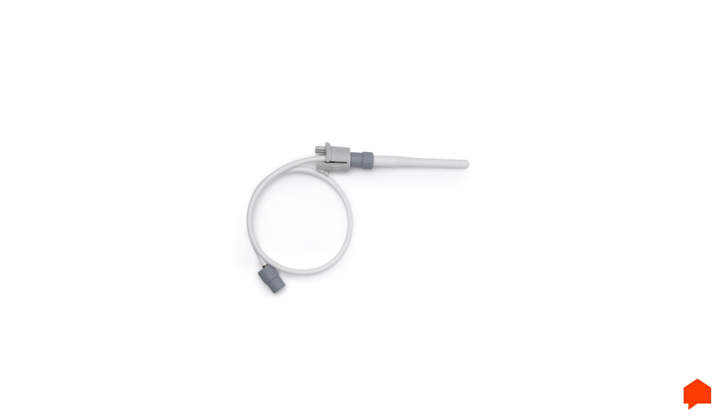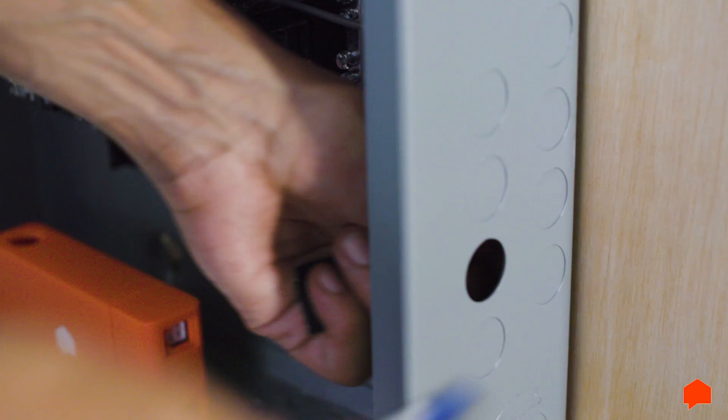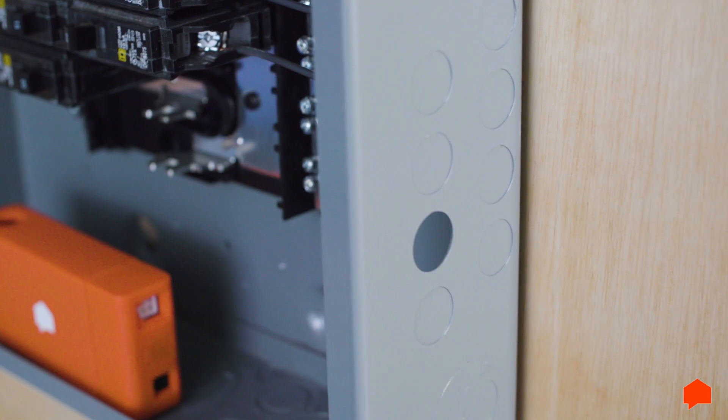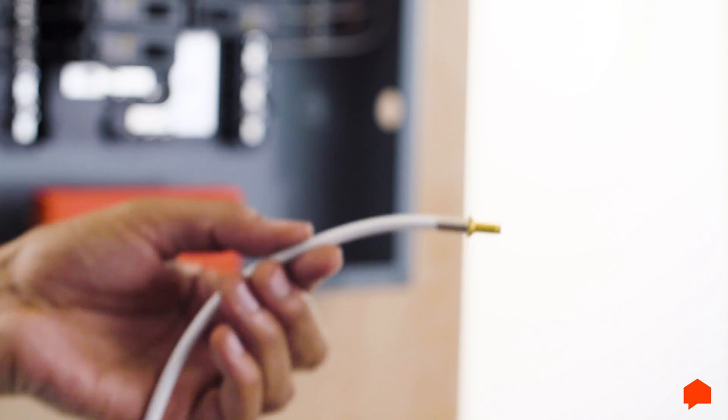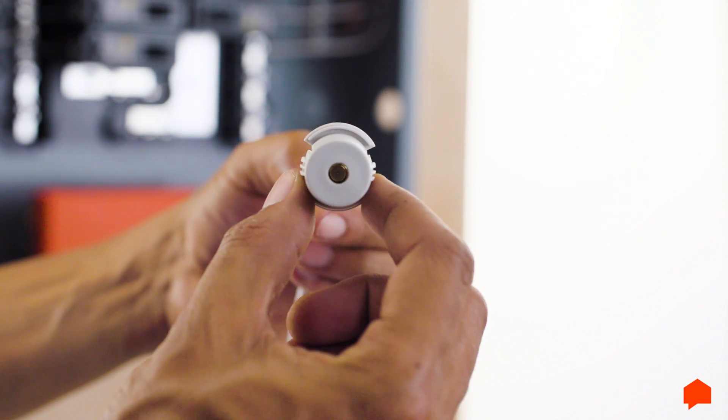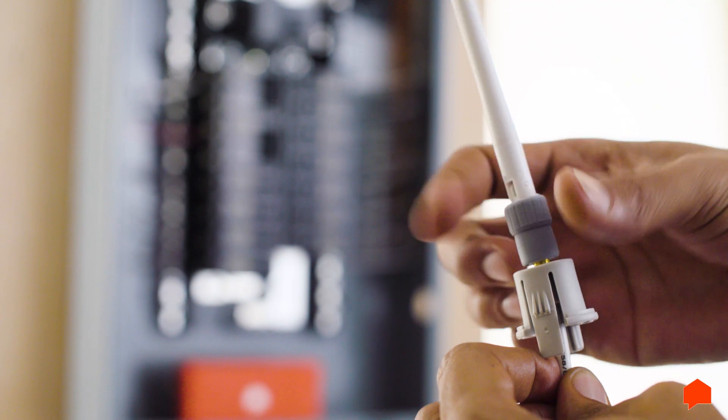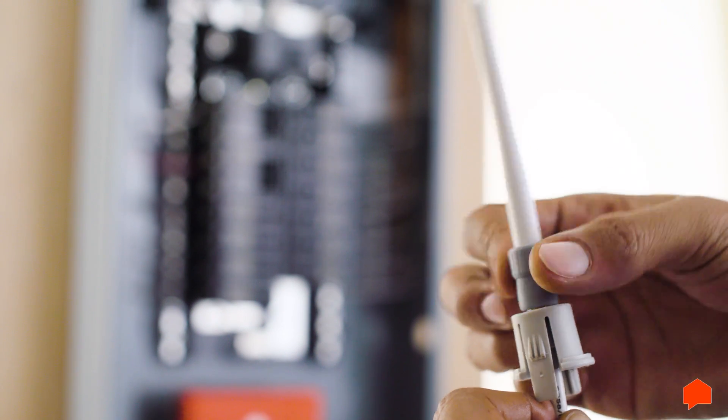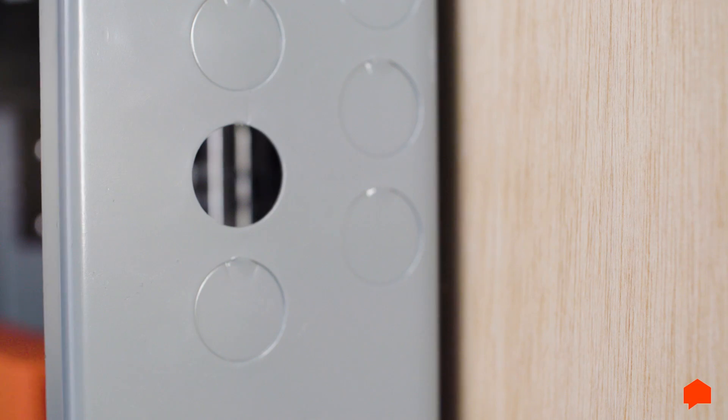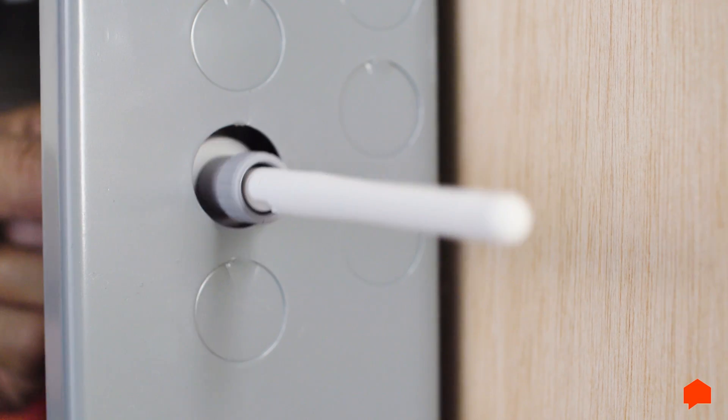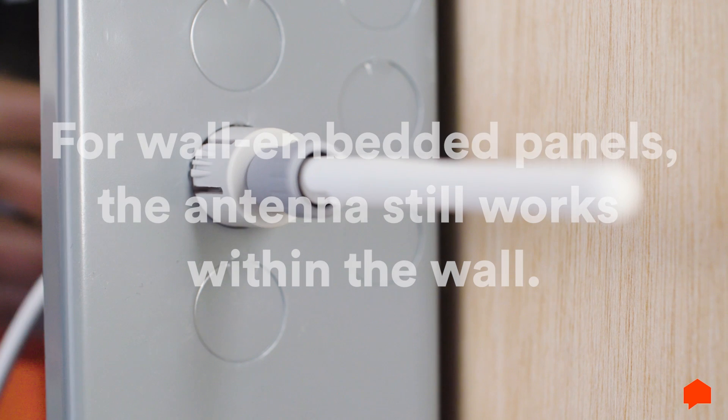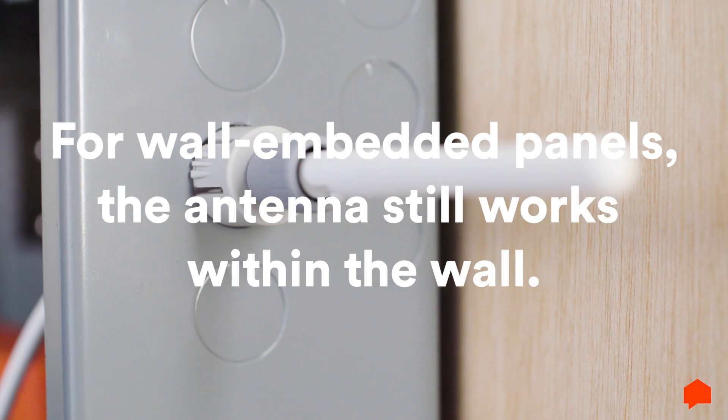The antenna needs to be outside the electrical panel, so remove a half-inch knockout from the panel. Slide the antenna insert onto the antenna extension cable, then screw on the antenna. Push the antenna and the insert through the knockout. If you have a wall-embedded panel, don't worry. The antenna functions just fine within the wall.